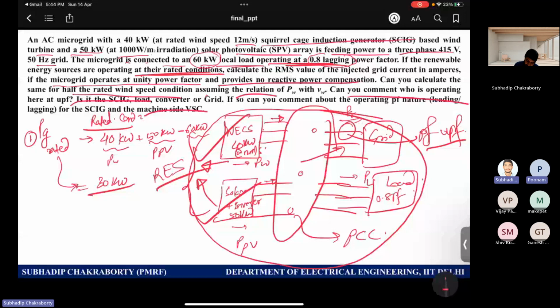The reactive power follows from the ratio of kilowatt and kVA, which is the power factor. Whatever parameter you know, you can calculate the other from these two. So I directly gave you the active power. Please check: if it's already in kilowatt, no need to redo it with the power factor. But if it's not, then you have to calculate the kilowatt rating.